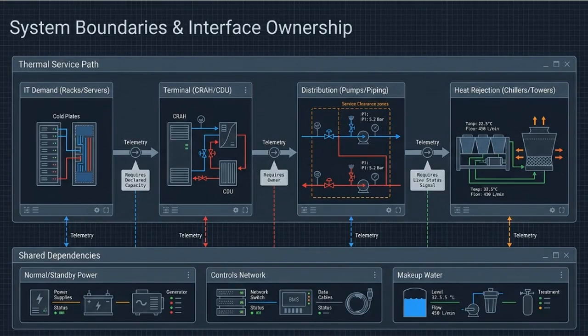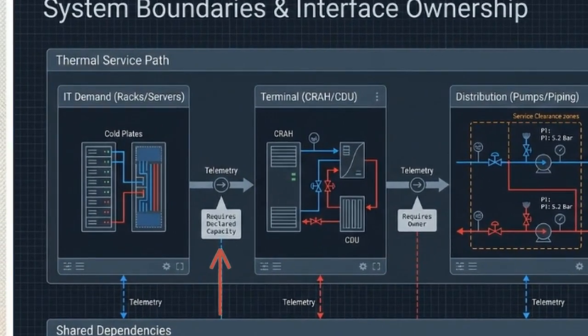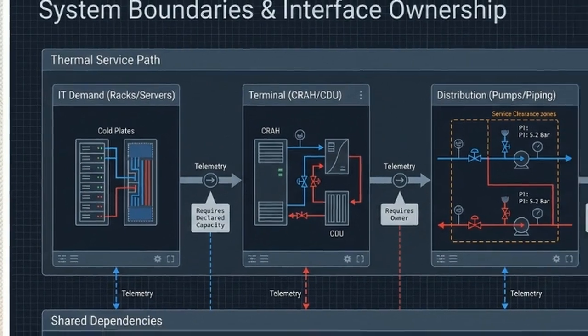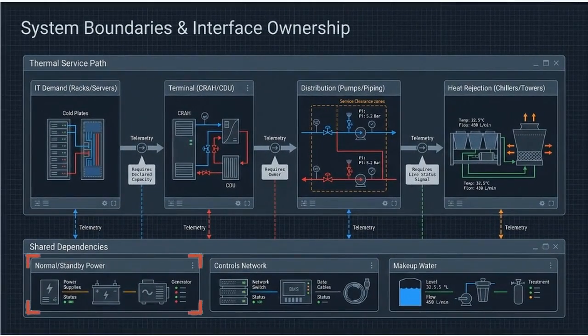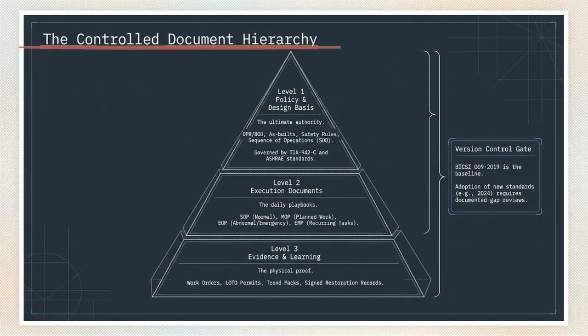Managing this thermal path requires defining strict interface ownership at every physical boundary. This flowchart tracks the system from IT demand on the left to heat rejection on the right. At every handoff point, capacity must be declared and acceptance confirmed. Below the main path are the shared dependencies that support these components. Standby power generators, control networks, and makeup water systems are single points of vulnerability that interact with the entire cooling chain. The physical plant is governed entirely by the controlled document hierarchy.